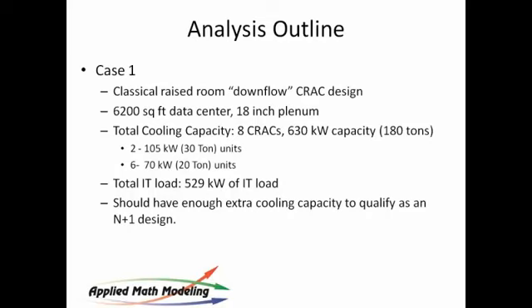The IT load here is only 529. So, you know, you look at this and you sharpen your pencil and you go, yeah, N+1. We should have enough extra cooling capacity for this thing to qualify as an N+1 design and to be able to run without one of these units on.